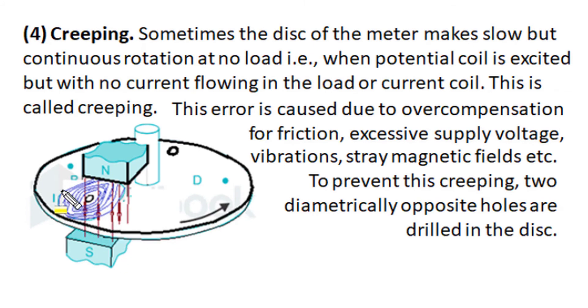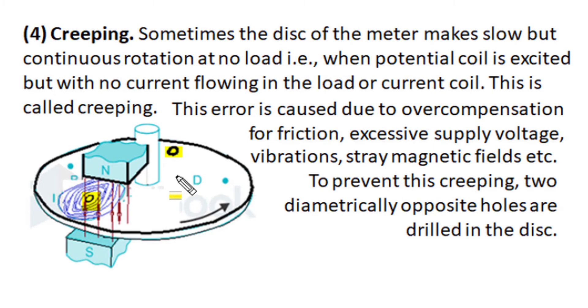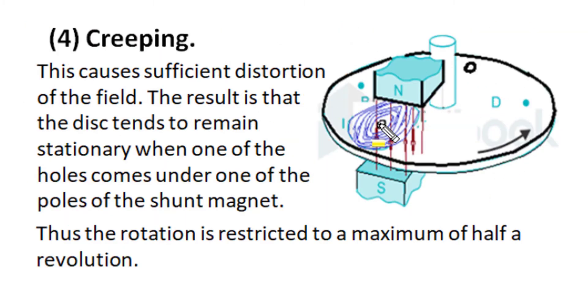Creeping is also a concern in disk-type energy meters. Sometimes the disk makes a slow but continuous rotation at no load — the shunt magnet is excited by voltage but there is no load current, so the series magnet is not excited, yet the disk starts slow continuous rotation. This is called creeping. The cause of creeping is over-compensation for friction, excessive supply voltage, or external stray magnetic field effects. To prevent creeping, two diametrically opposite holes are drilled in the disk. Even when light load adjustment has over-compensated friction, the disk won't rotate more than half a turn.